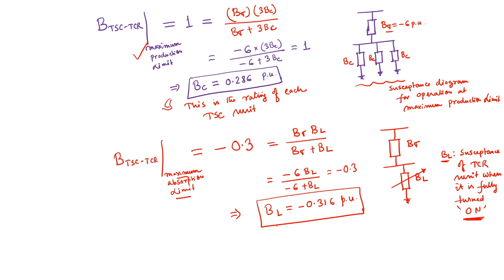So we got the susceptance of the TCR unit, and we got the susceptance of each capacitor unit. This is how we determine the ratings of each TSC unit, susceptance rating to be more precise, and also the maximum susceptance rating or rated value of the susceptance of the TCR unit.